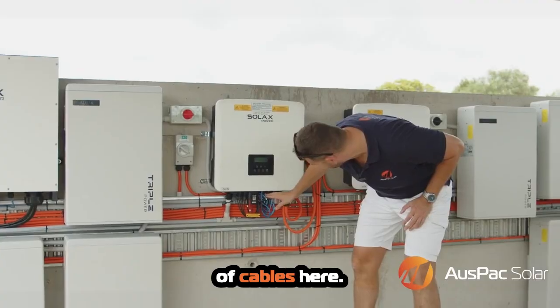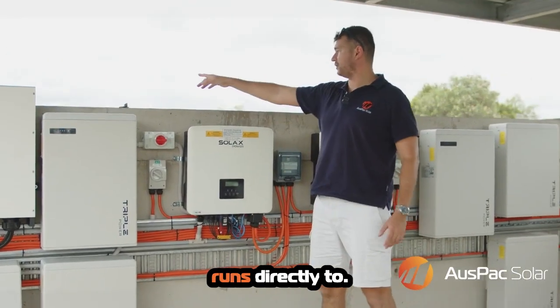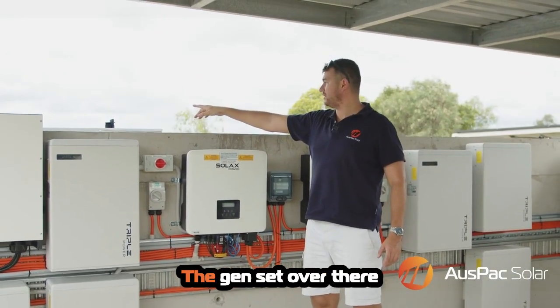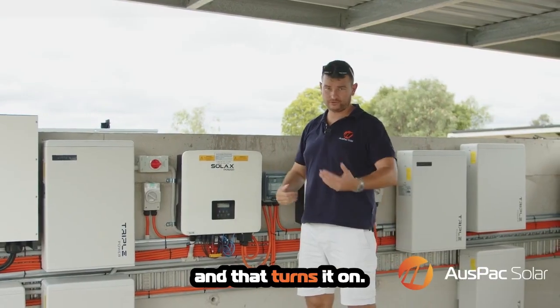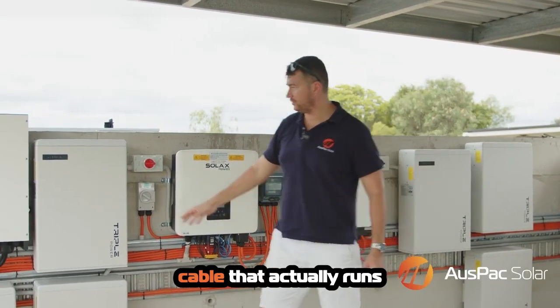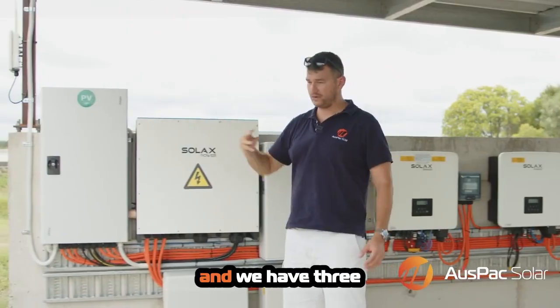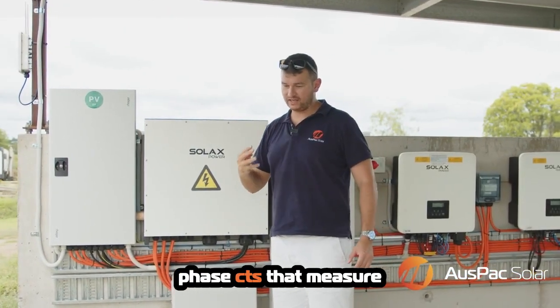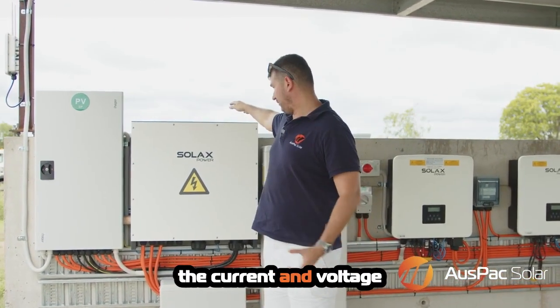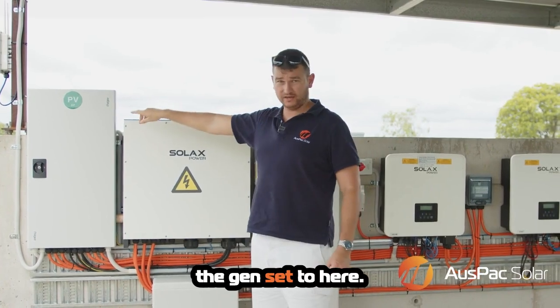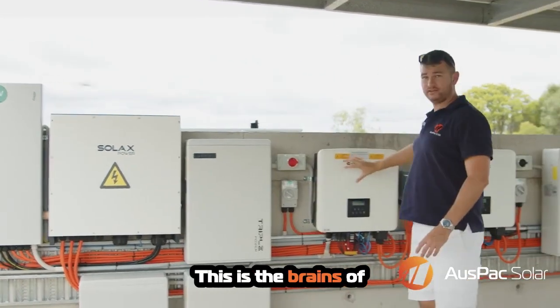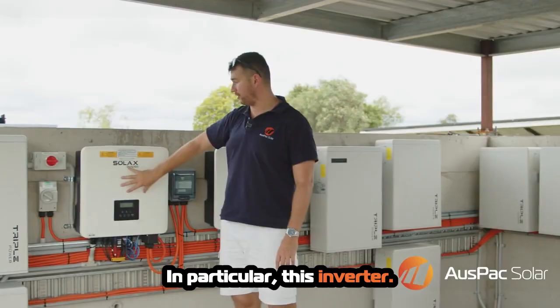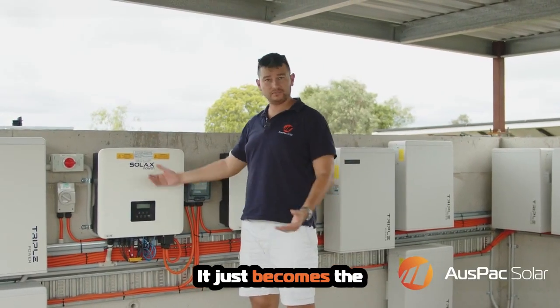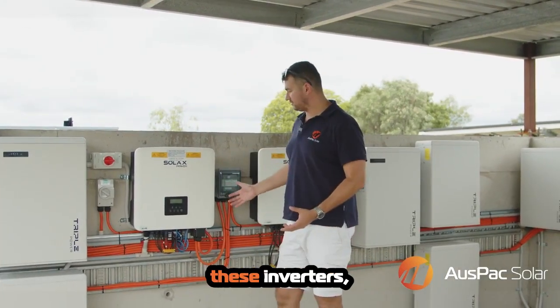There's a number of cables here. We've got our other data cable, which runs directly to the genset over there, and that turns it on. We have another data cable that actually runs back to the switchboard, and we have 3-phase CTs that measure the current and voltage that is running from the genset to here. This is the brains of the whole operation, in particular this inverter. It's not a special inverter, it just becomes the master inverter. They're universal, these inverters, which are great.